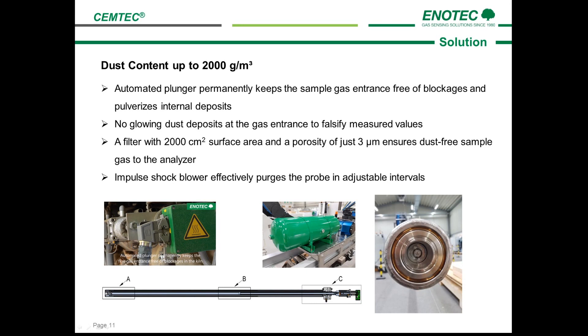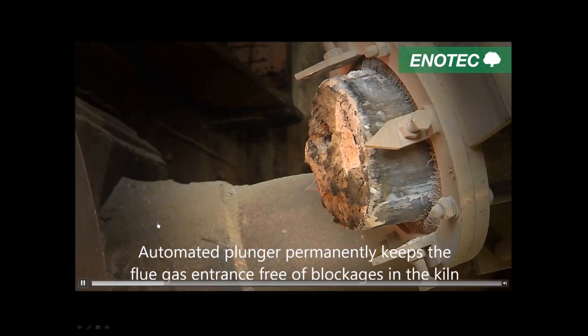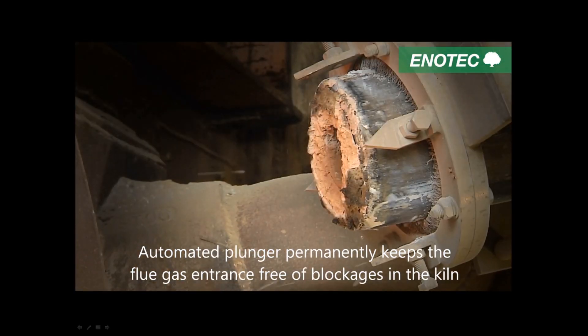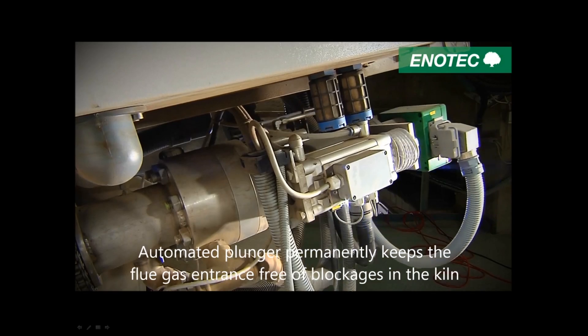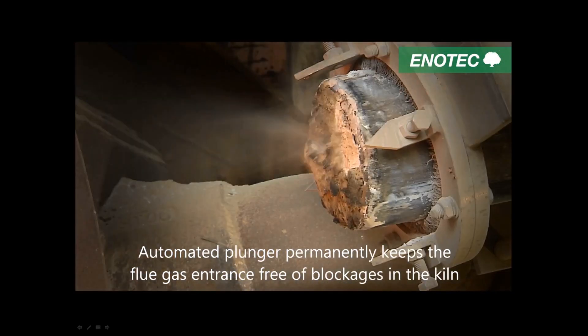Another difficult challenge to overcome is the extremely high dust content of around two kilograms per cubic meter inside the kiln. The combination of high temperatures and high dust concentration makes this a difficult application. CEMTEC has an automated plunger which permanently keeps the flue gas entrance free of blockages and pulverizes deposits within the probe. Blockages will falsify the measured values of O2 and CO. Here is a short video showing the plunger in operation.